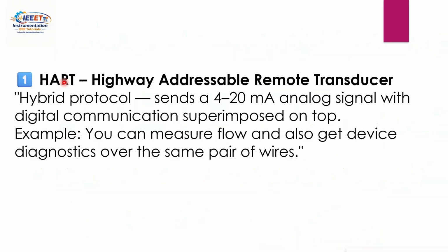The first is HART. The full form of HART is Highway Addressable Remote Transducer. The T means transducer. This is a hybrid protocol because it sends a 4-20 milliampere analog signal with digital communication superimposed on top. It is hybrid due to the 4-20 milliampere analog signal as well as digital signals. For example, you can measure the flow and also get device diagnostics over the same pair of wires, meaning you can get diagnostic parameters like alarms as well. So HART, the Highway Addressable Remote Transducer protocol, is a hybrid protocol.